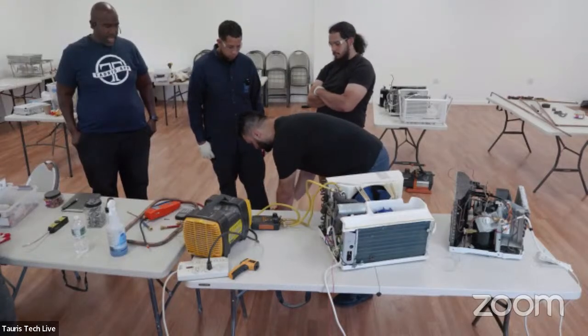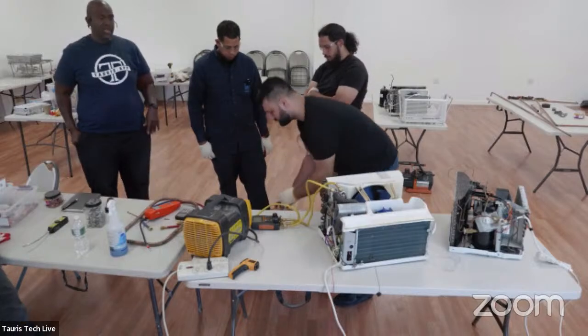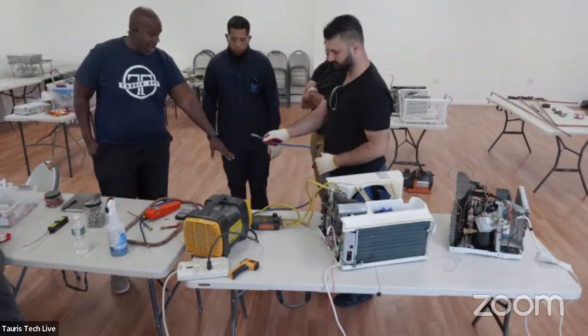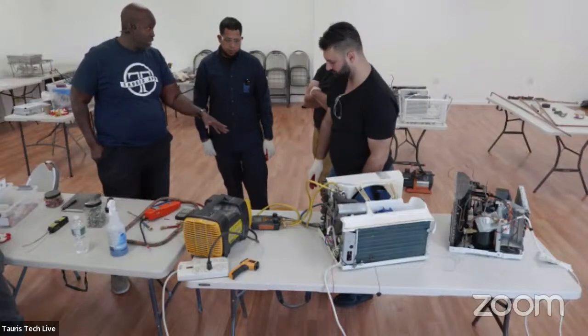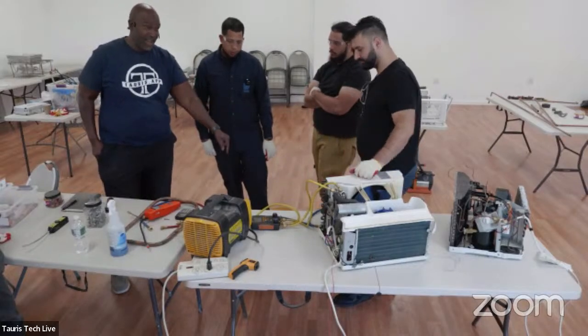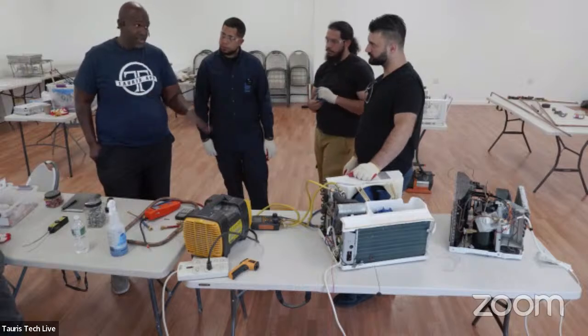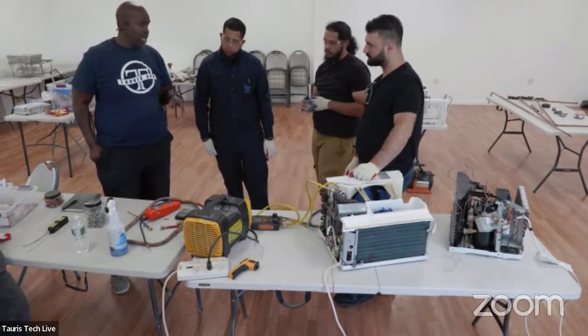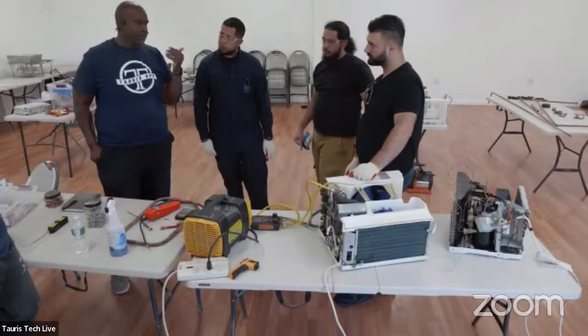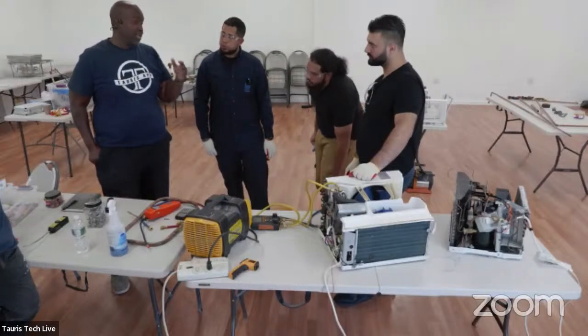So as you can see, because I'm going to the vapor valve, there's not as much liquid as there would be if I was on that liquid valve. If I was on that liquid valve, there'd be refrigerant spray all over. And when you see mist, it's not refrigerant, it's oil, because we're recovering oil as well.